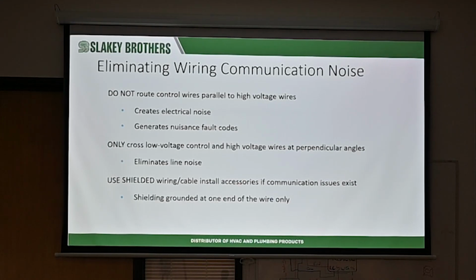Because you're going to get that customer saying, hey, it's doing it again. It could be a week later, a day later, an hour later, or a year later, a constant, every-so-often interference. This is one of the things you have to do, is make sure it's not around electrical. Because otherwise, this is the biggest problem, callbacks and the nuisance thing, and you're like, it's working. It's working now, I don't know what to do. So you run into a situation like that, communication faults.